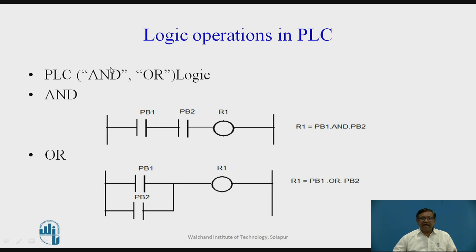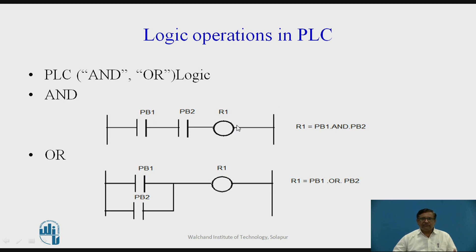Here we are implementing AND and OR logic operations using a ladder diagram of a PLC. This is the ladder diagram for the AND logical operation. If you look here, this is push button 1, this is push button 2, and it is connected to the output called R1. This ladder diagram consists of only one rung, and rails are present — one is called line and another is called neutral in case of AC supply, or positive and negative in case of DC supply.